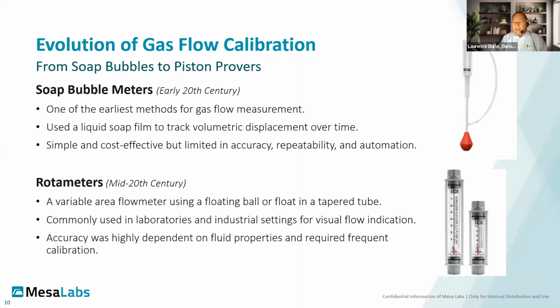Rotameters came in. It's basically a variable area tube, a tapered tube. Air or gas comes in at the bottom. It pushes a ball or a float up to some sort of a calibrated mark. You see it a lot in laboratories and industrial settings right now, just as a visual flow indicator. The accuracy was not real good. It depended on fluid properties. You had to have frequent calibration. Just the tiniest bit of buildup along the walls of the tube would cause false high readings. We try not to use them currently, particularly the ones that look like they came in the prize in a box of Cracker Jack.